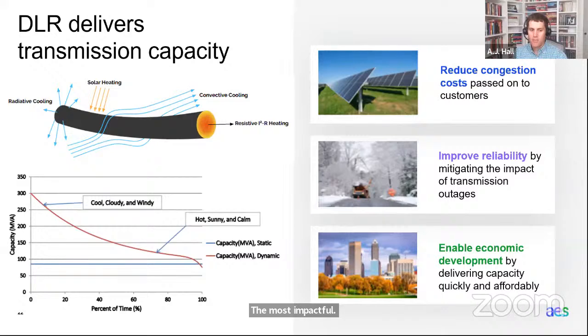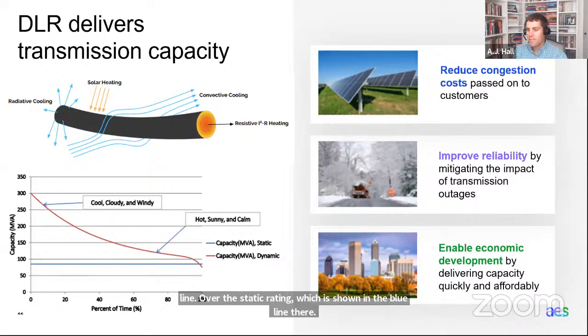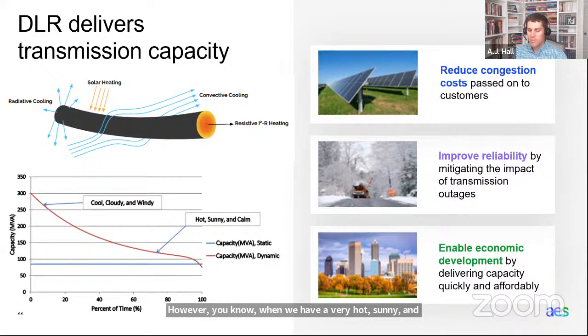You can see at the graph at the bottom that on a cool, cloudy, and windy day, you may have 2 to 3 times the capacity on a transmission line over the static rating, shown in the blue line there. However, on a very hot, sunny day with no wind, you can see toward the right-hand side of the graph there are times when our transmission lines may be operated at a level too high for their true capacity.